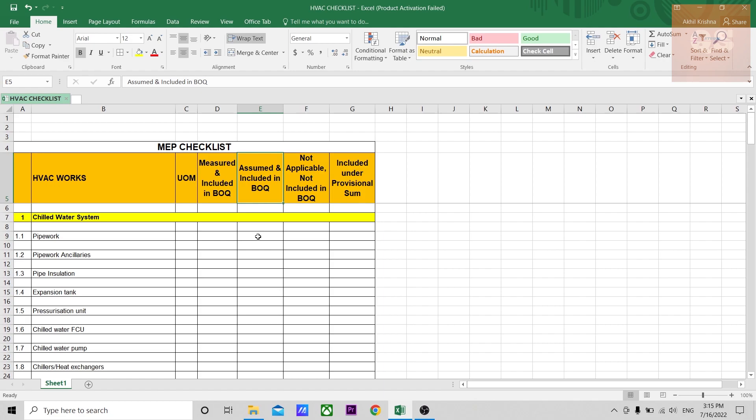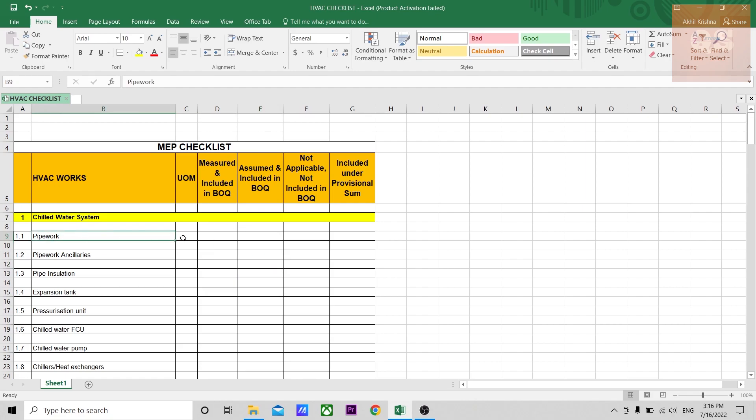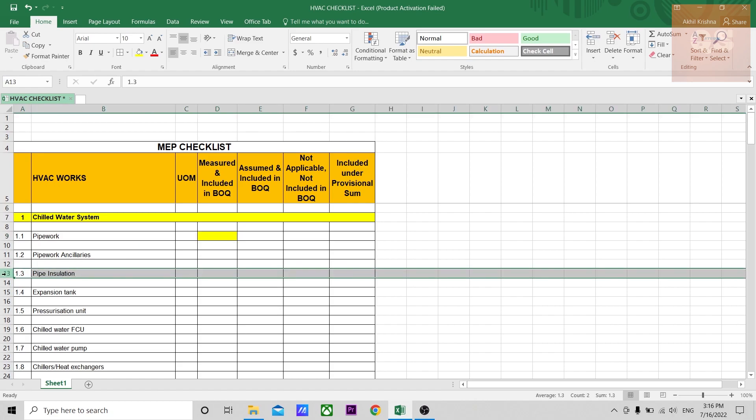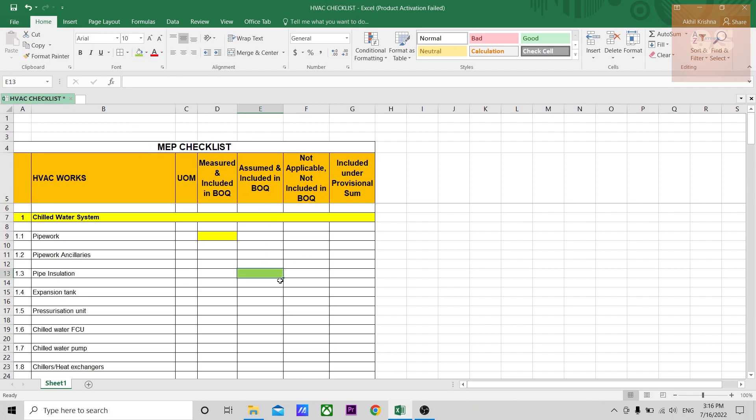There might be some items you'll have an idea about the system that this particular item should be coming, but it's not shown in the drawing. You can assume such items, like for example small ancillaries, dampers, or diffusers. Sometimes it will not be shown in the drawing. Maybe the designer would have forgotten to mention it, so you can assume and count and put those items. Items that have been assumed can be put in another color and marked. For example, if pipe work is measured, you can put a color yellow. For pipe insulation not given in the drawings or specification or nowhere in the project documentation, you can assume pipe insulation should be coming and put another color for whatever you assume.